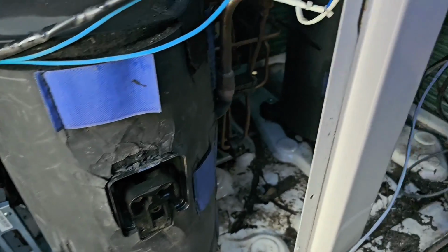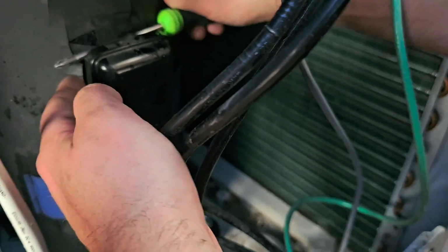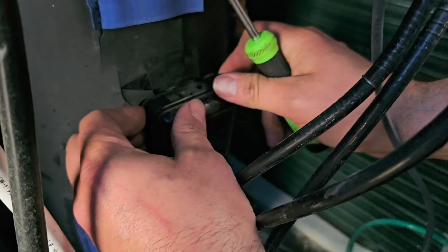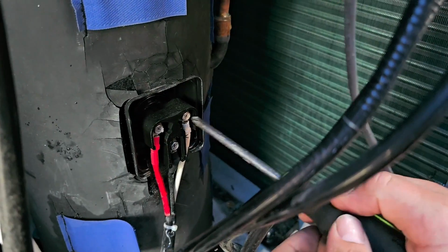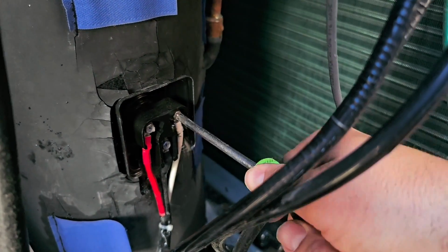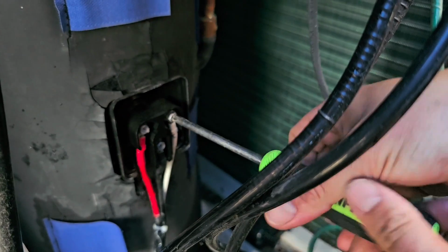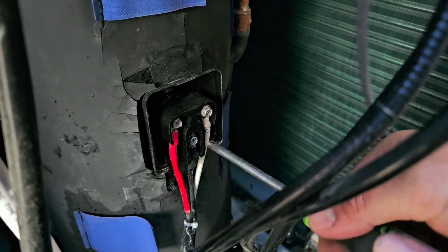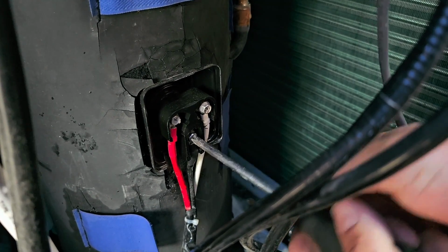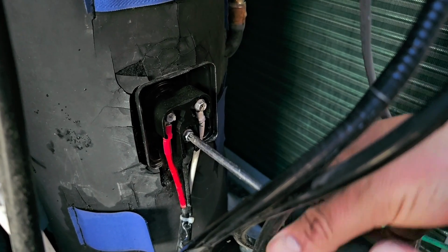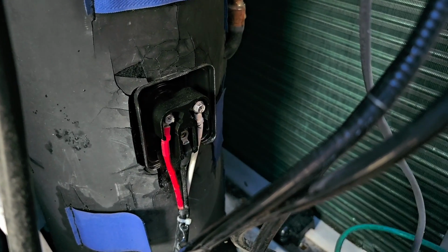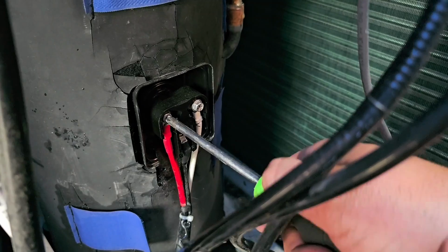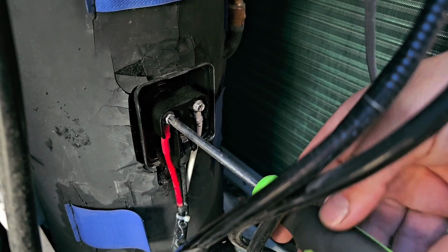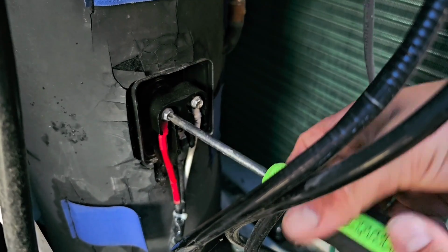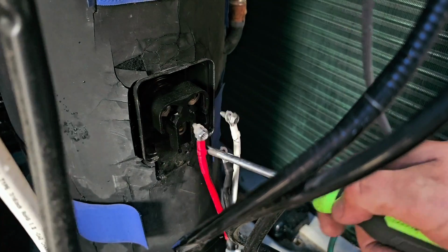Now that we've disconnected the wiring from that compressor, we're going to do the same thing to this compressor. So remove the cover, and then we will loosen up these 3 screws. And you don't want to use a drill and a Phillips bit. You want to actually use a Phillips screwdriver. That way you don't over tighten the terminals. All right, we'll get these wires off, and that one's isolated now.